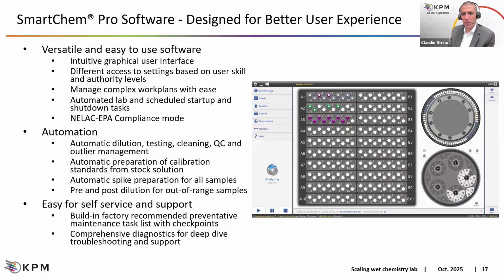But in any case, there is a maintenance schedule table inside the software that will remind you what maintenance needs to be done. In any case, it is to clean the needle, and when needed to replace cuvettes, because cuvettes can be replaced as a single cuvette, and you don't need to replace a full set of cuvettes, but individually. And then it also depends on the agreement between the lab and our local representative, because we have some labs having internal maintenance service engineers that we are training, and they will take care of the full maintenance and service on the unit. So replacing the lamp when needed, replacing cuvettes, washing the inlet tanks, cleaning tubings, performing the wash of the system. So it depends on the level of maintenance that the lab would like to assign to the operators.